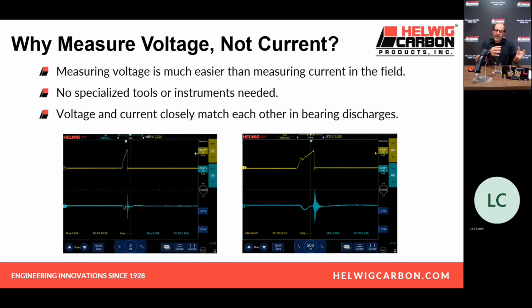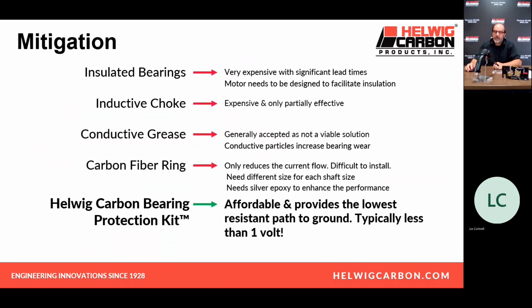When you measure current, the accuracy of the reading very much depends on the setup of the test itself. As you can see, when you measure voltage, current follows voltage. So if we can detect a voltage spike, the current spike follows it. As you can see in the slides below, the two are very, very closely related. If you see one, you're seeing the other. So we measure voltage because of the ease at which it can be measured accurately.